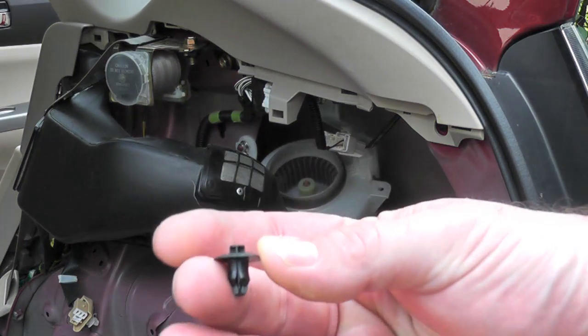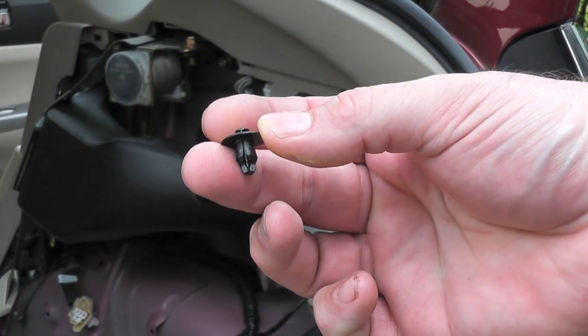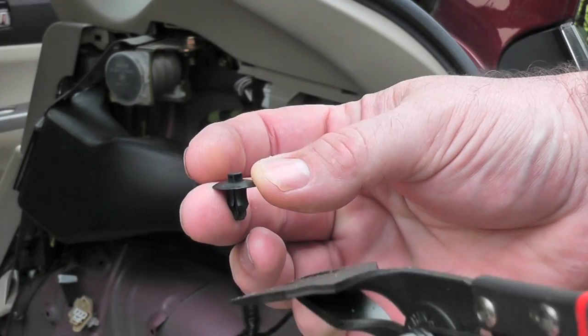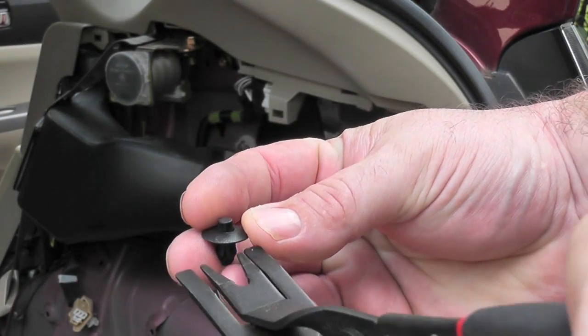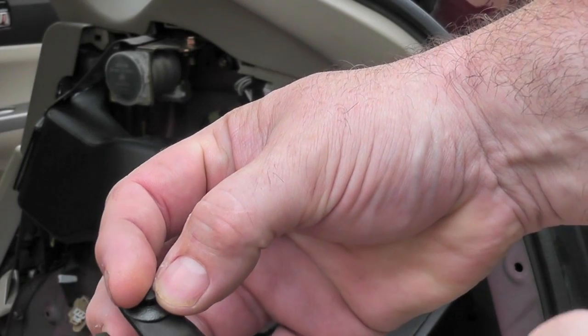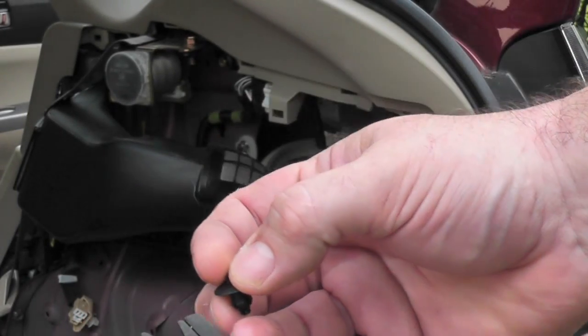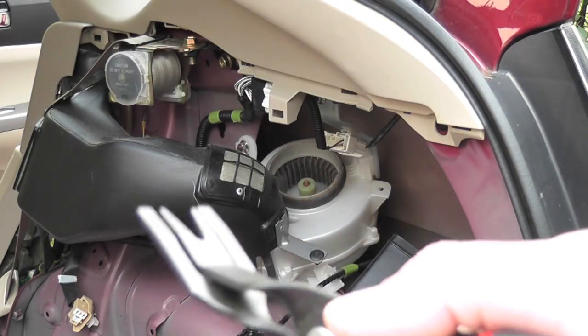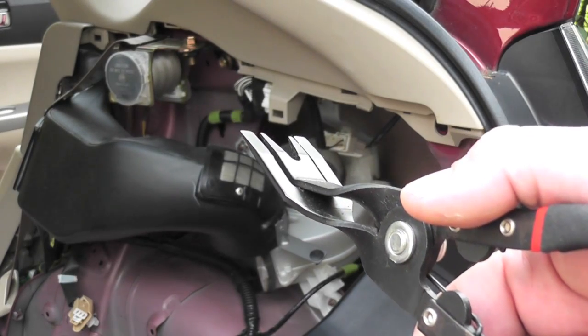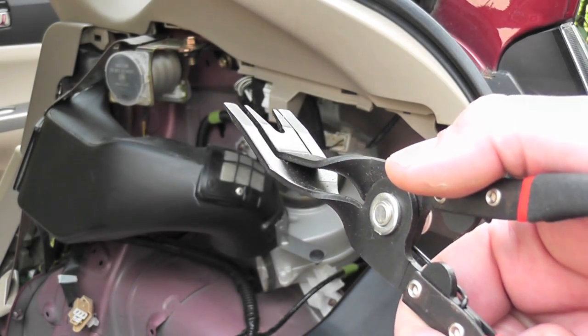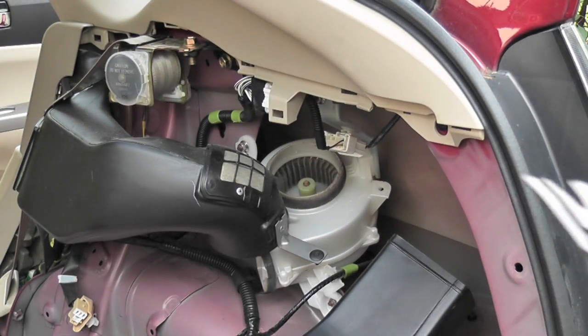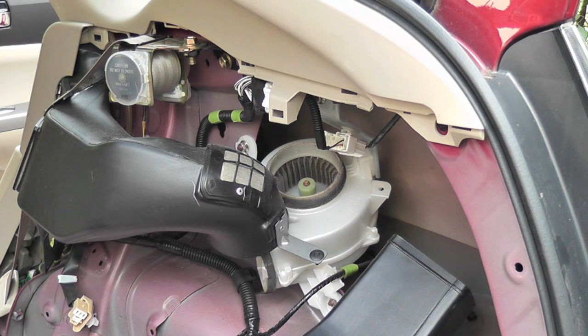Here is one of those push pins that holds it in. You slide this device underneath the push pin, and then pop it up like that. That creates leverage and pops it loose. It takes quite a bit of leverage, but once you have that, it'll pop loose with a loud pop, and it'll come off. There are 3 of those holding the ductwork in place, so you need to release all of them to get to the fan blades to clean them.